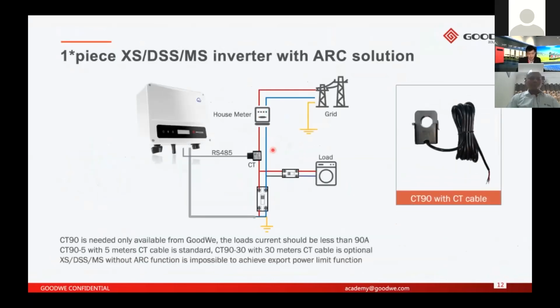And this one is one piece, XS/DSS/MS inverter with ARC. Okay, it was already introduced just now. It's the same as the NS and DNS with ARC solution. So you just need to buy the CT90 from GoodWe and connect the CT to the inverter directly. So it's very simple, and the CT cable is optional, 5 meters or 30 meters.